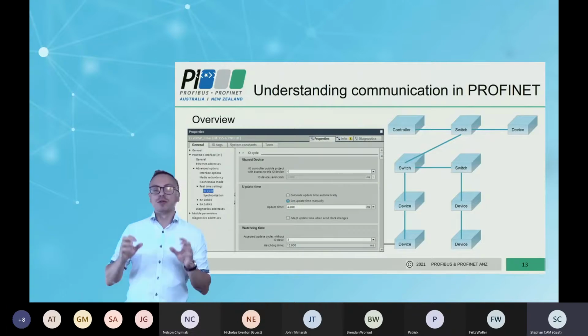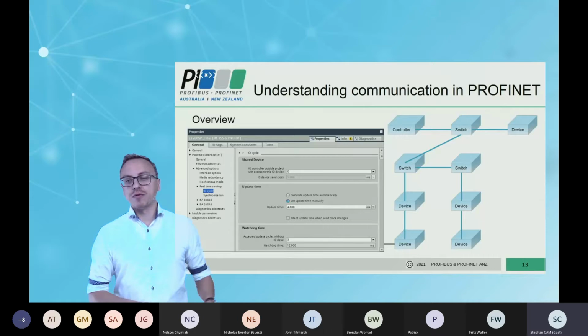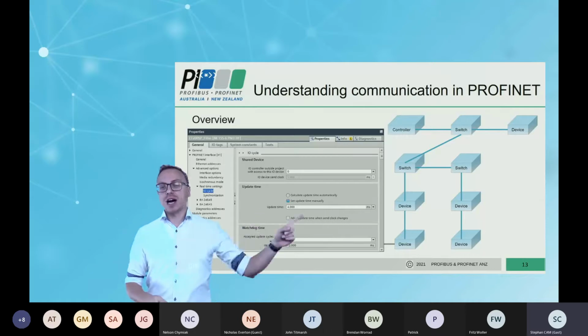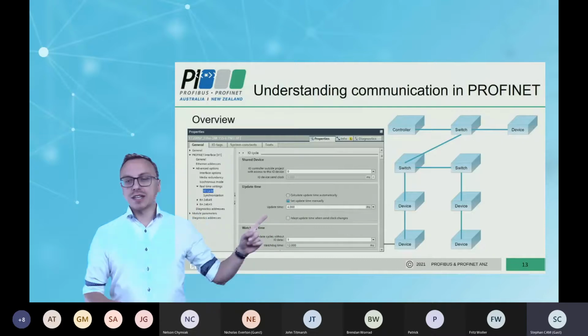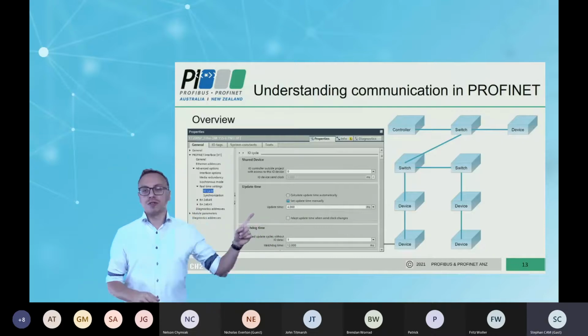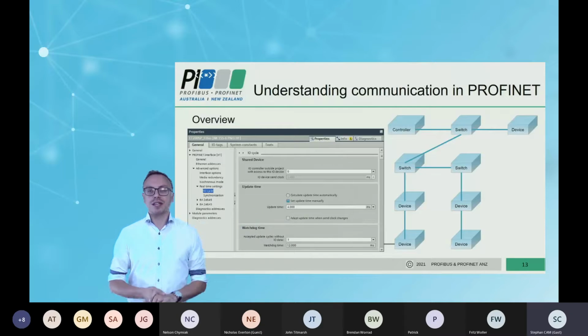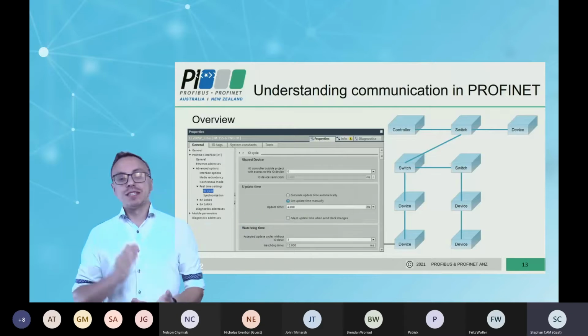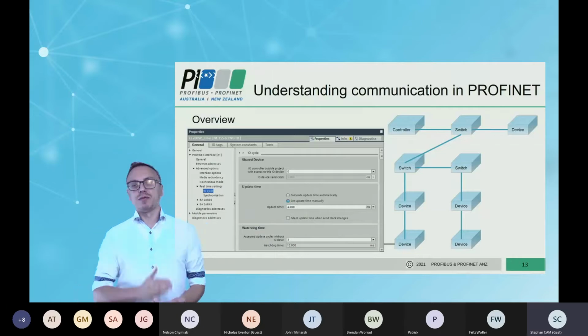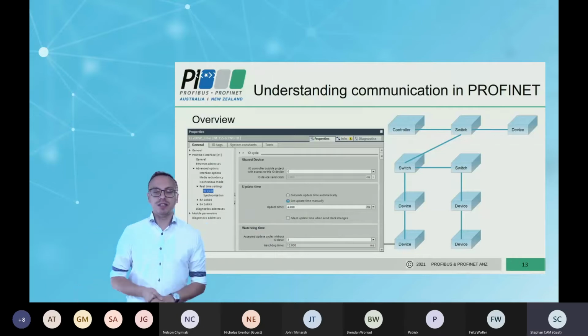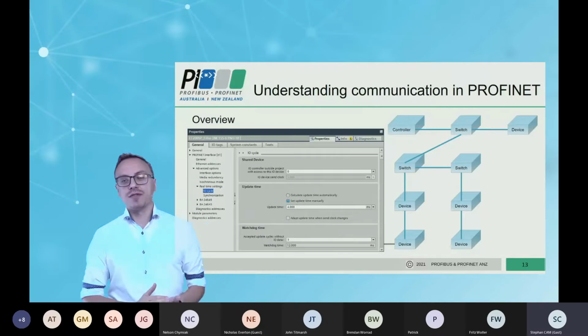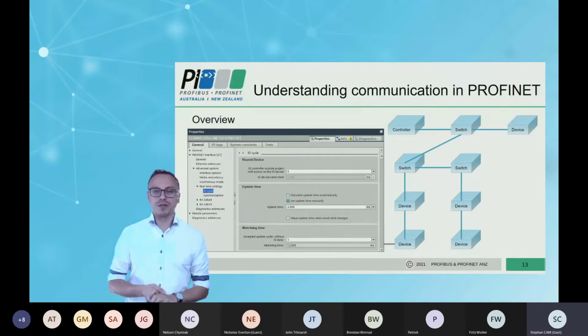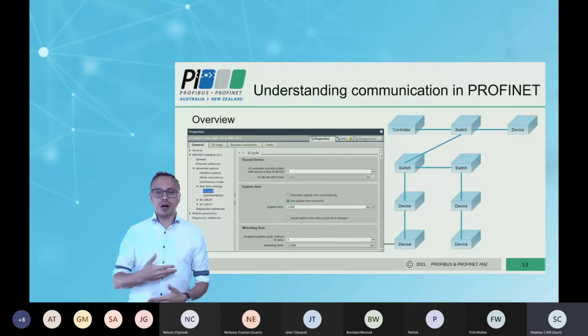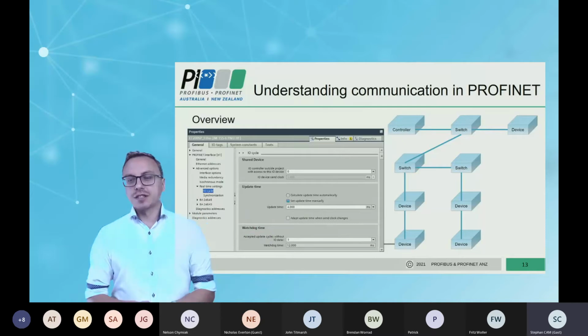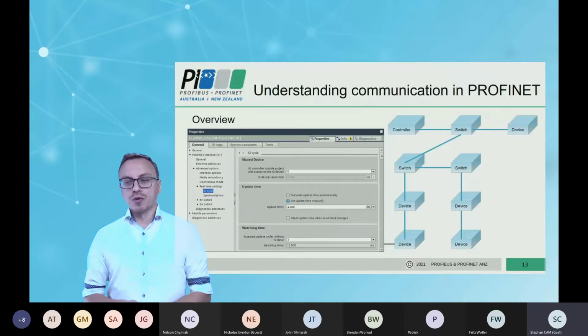If you go into the hardware configuration, you can configure for each device the update time and the watchdog time. What does the update time mean? In this example, you can see we configured this device with an update time of 4 milliseconds. That means this device will send information to the PLC every 4 milliseconds, and the PLC will send information to this PROFINET device every 4 milliseconds. So this is a normal input-output communication, and this is how it works in PROFINET.